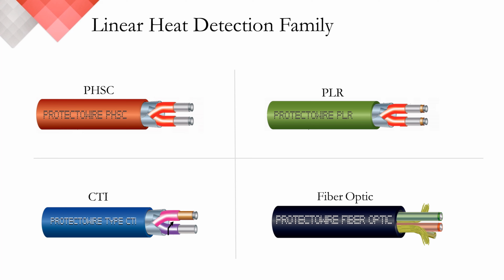Next is the PLR series, which stands for Protectowire Low Resistance. Same construction as PHSC, the PLR series adds copper-coated conductors to reduce the cable's overall resistance value from 0.185 ohms per foot, which is the standard resistance value of steel, to 0.058 ohms per foot. That's roughly a 2/3 reduction in resistance value. Lower resistance equals longer runs. The most recent development in linear heat detection is CTI, which stands for Confirmed Temperature Initiation. Replacing the steel core conductors of our standard PHSC series with copper and constantan creates a Type T thermocouple, providing us the ability to measure physical temperatures at the location of the fault. Through the required CTM530 interface module, we can now program the initiation temperature and compare it to the temperature of the fault. Through this process, we can discriminate between a mechanical failure and an actual true heat event.